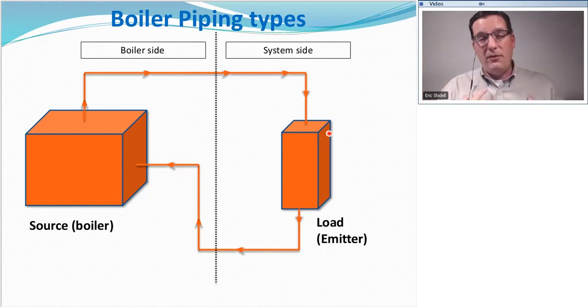And I've personally been involved in lots of these situations. Some of them I caused myself. But as I got more experienced, it was more me going afterwards and saying, hey, they're still having a problem. What can you find out? And come to find out that the technicians were always in the boiler room, didn't see anything wrong, but the problem was out in the system. So just be really conscious that what happens out here affects what happens in here, and vice versa. What happens in here affects what happens out here. And that's how it's supposed to work, right? We have this heat source here, the heat delivery out here. Well, if you can't deliver it very well, you're going to have problems over here. But the solution ends up being over here. So don't forget about the system.